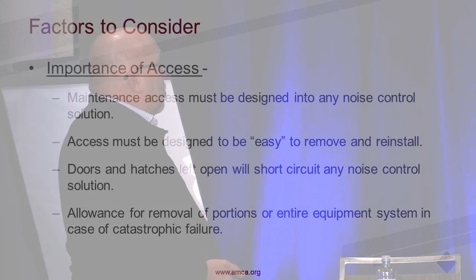I was always taught that if you put in a noise control solution—say on an exhaust fan, an upblast fan where noise is propagating out the discharge and neighbors are complaining—the silencer should not sit directly on that fan to that extreme. It should be externally supported. The equipment wasn't meant to support that, and it wasn't designed for seismic loads, snow, or wind moment forces. So always make sure everything is externally supported and not supported by the equipment itself.